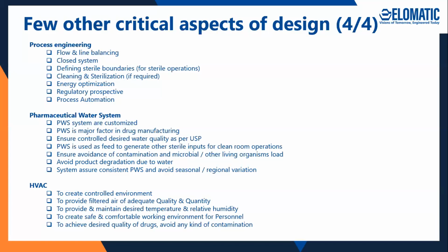HVAC - heating, ventilation, and air conditioning - has to be appropriately designed considering the heat load, the number of people present in the clean rooms or warehouse, the kind of operation being carried out in that suite, and whether it requires pressure control or a cascade effect. This has to be visualized at the design stage.